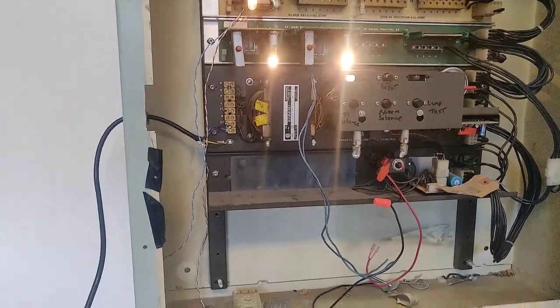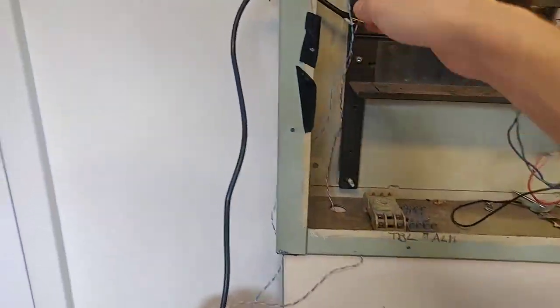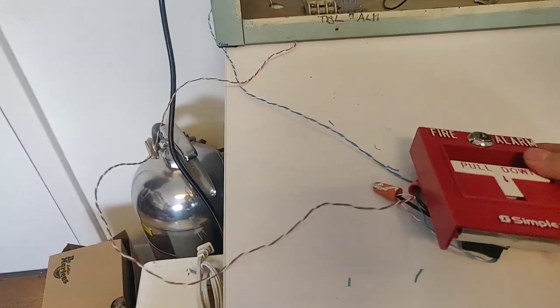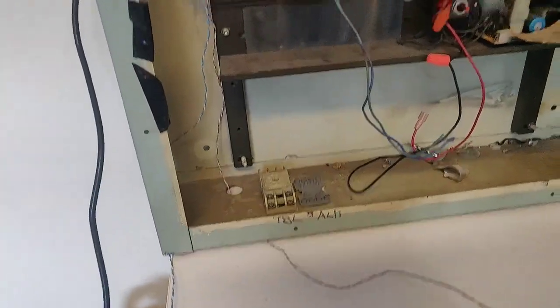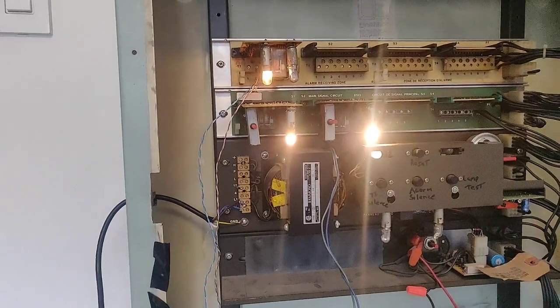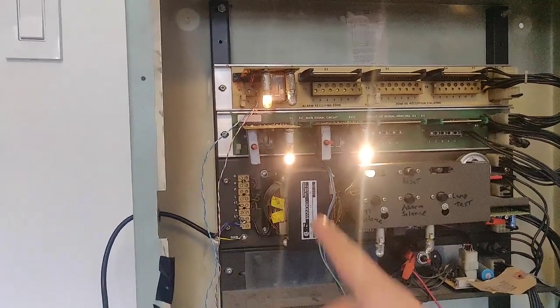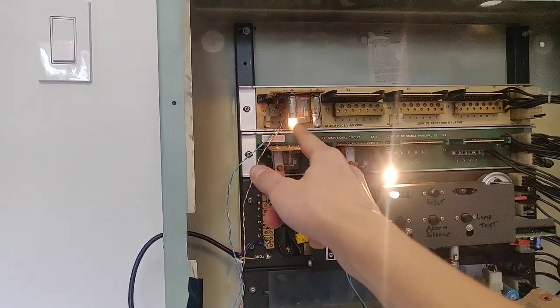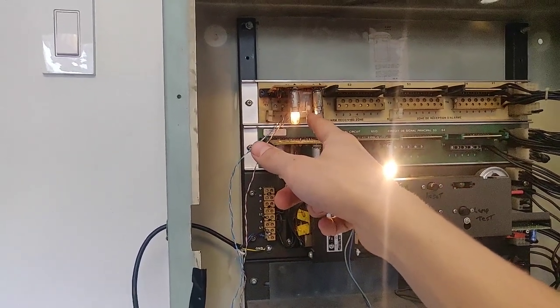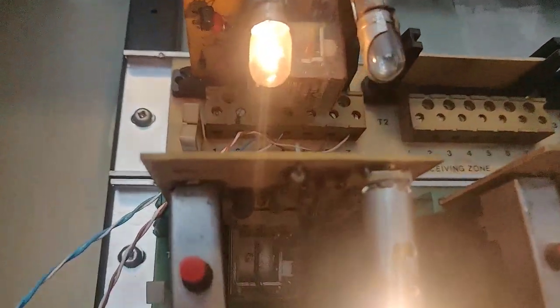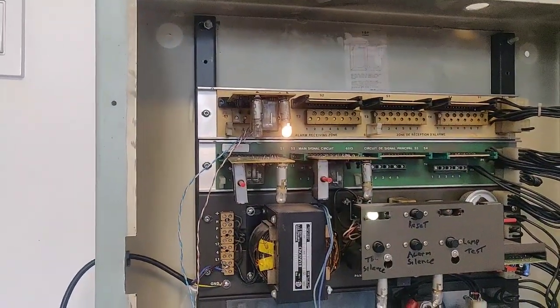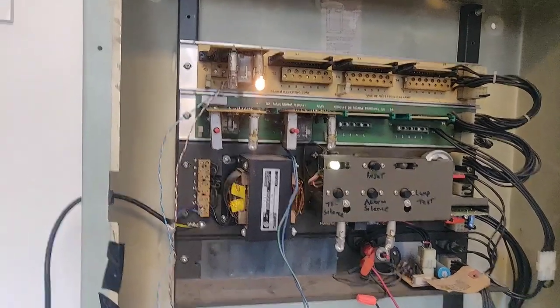So let's now move on to wiring the class A circuit for the initiating. Alright, so now it's wired in the class A manner. So we have one wire, one set of wires running out to our device, and then one—pretend it's in another conduit—coming back into the panel. The reason why we have a trouble light is that this card is not the one that's designed for class B—or sorry, class A. This is the class B model of the card. You can get a class A card and a class B card. This one is not compatible with class A. That's why it's in trouble. But one thing that's important to remember is that you get these polarities here correct, because if these are not correct the system will automatically go into alarm as soon as you power it on. So we can see that it works when we pull the pull station. System is in alarm.